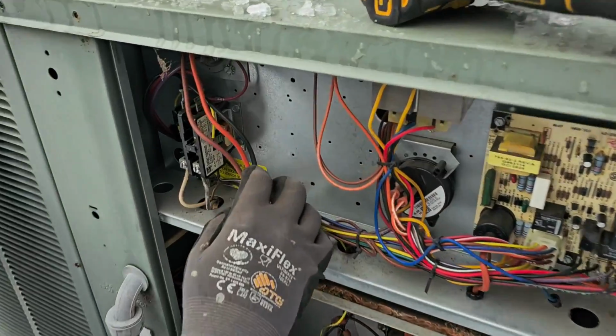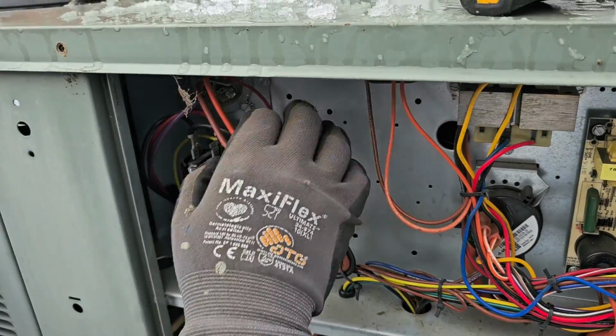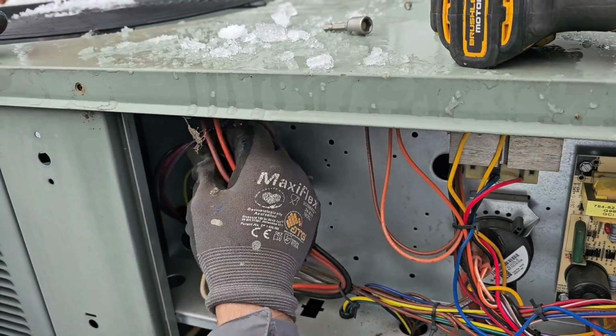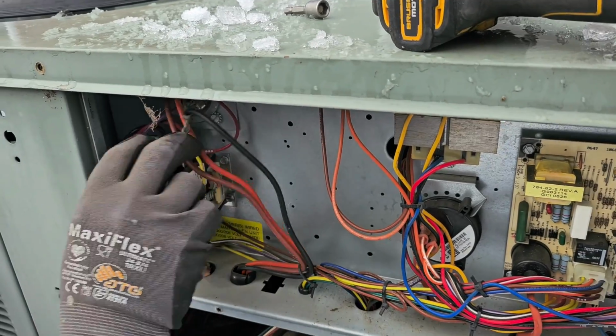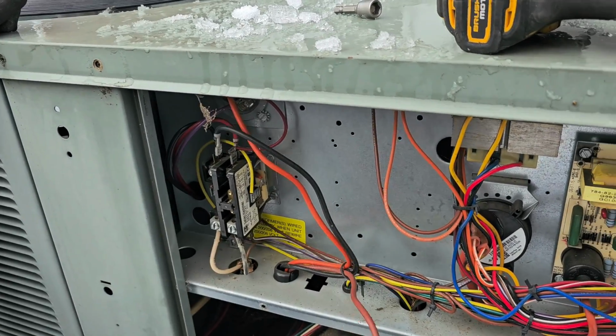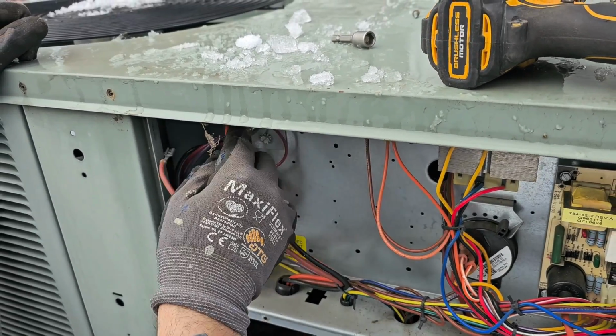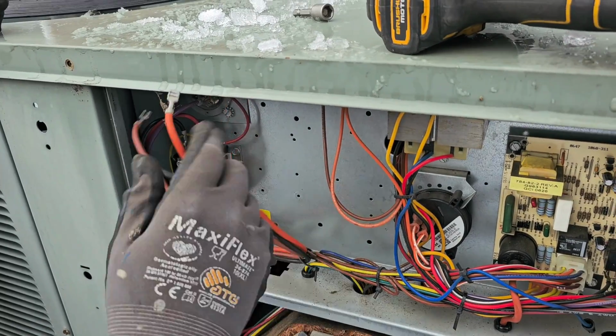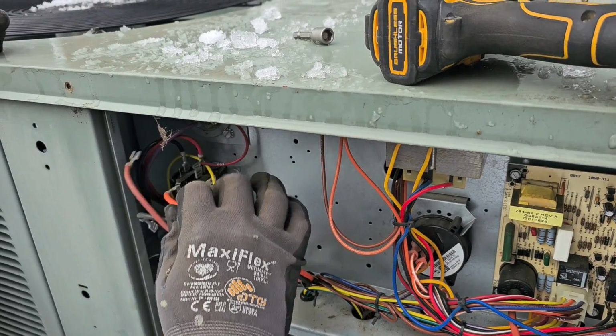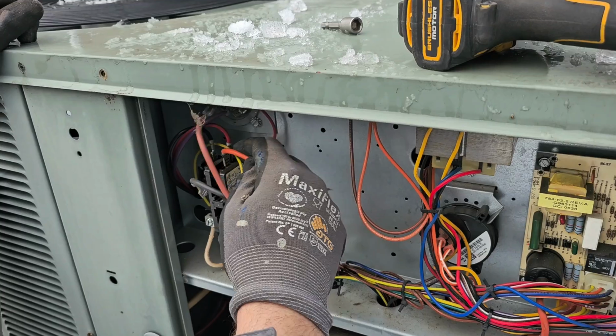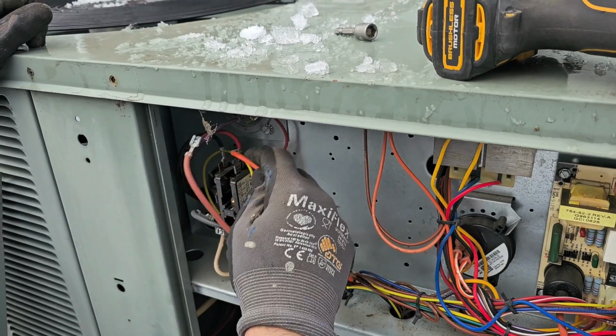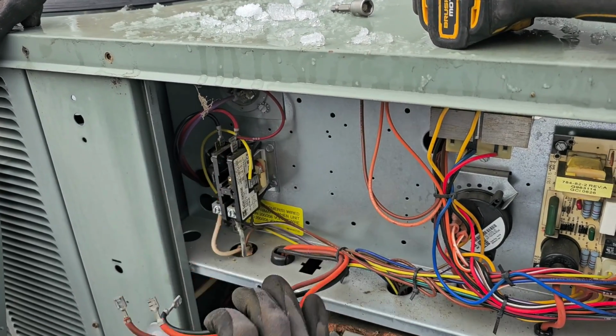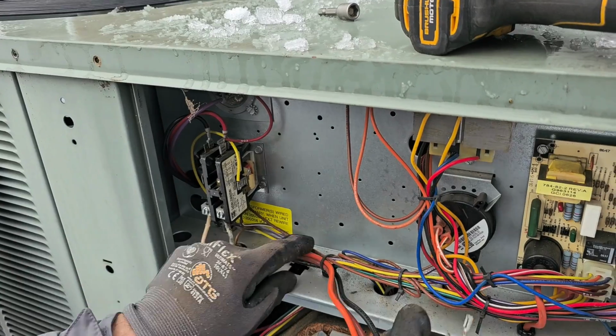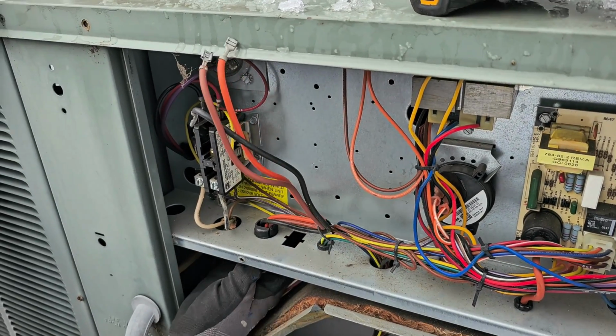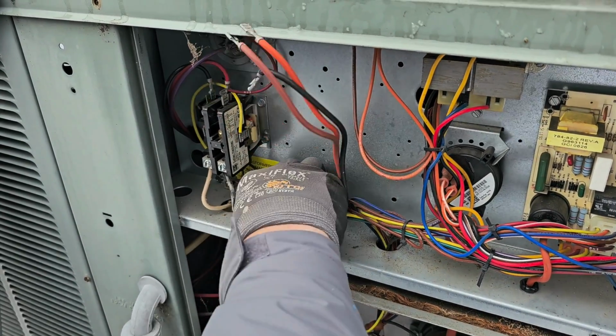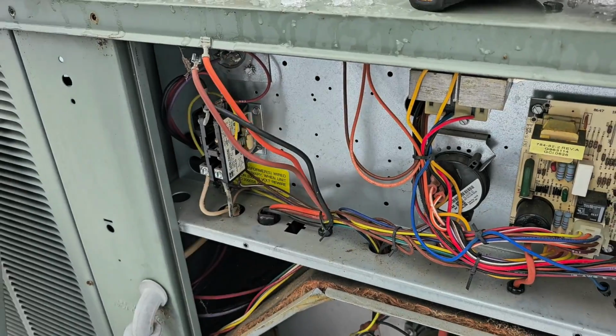All right, wires for the fan, pretty simple. Your black is one side of your power to your fan motor right there. Your brown goes to the F terminal of the dual capacitor. Your orange goes to the common terminal. You could also put this on the contactor terminal right here where the red wire goes. So you need to cut that wire tie and then pull these wires down here, and then our outdoor fan wires will be disconnected.